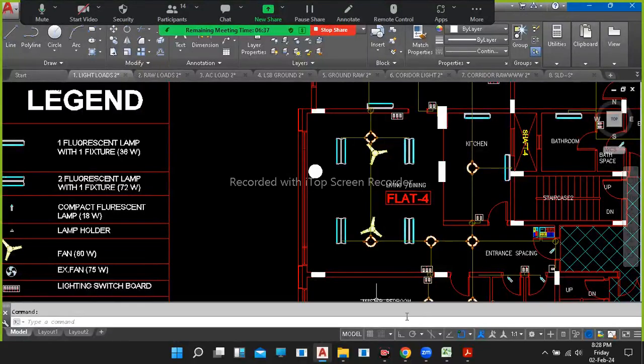From DB also—don't compare again with a residential building. Generally in a residential building they'll run only one single conduit, 25-40mm. But when you're going with a high-rise building, for lighting it is 20mm, for raw power it is 25mm.